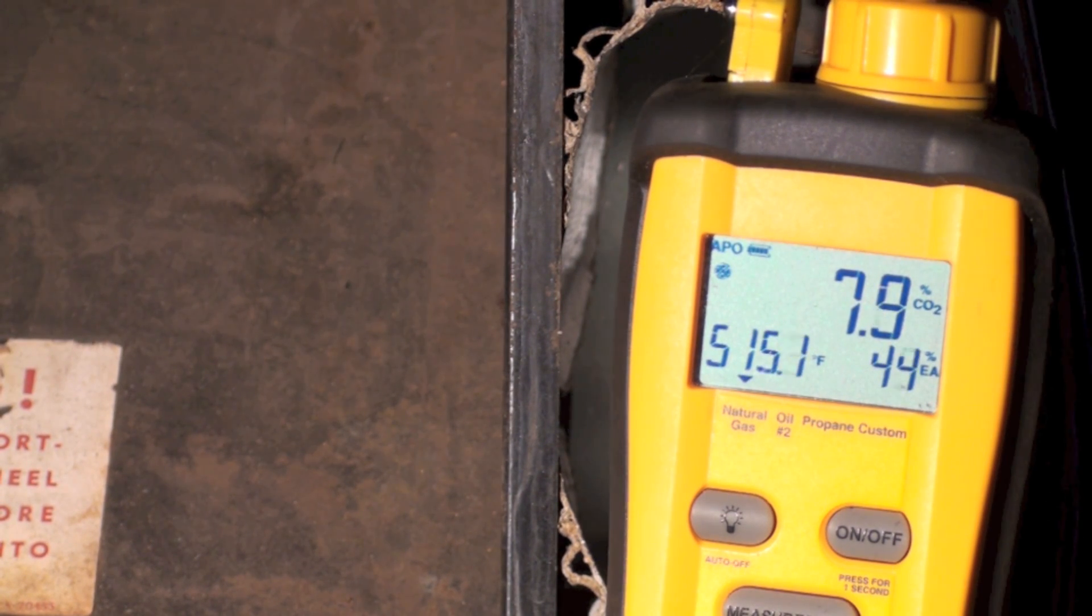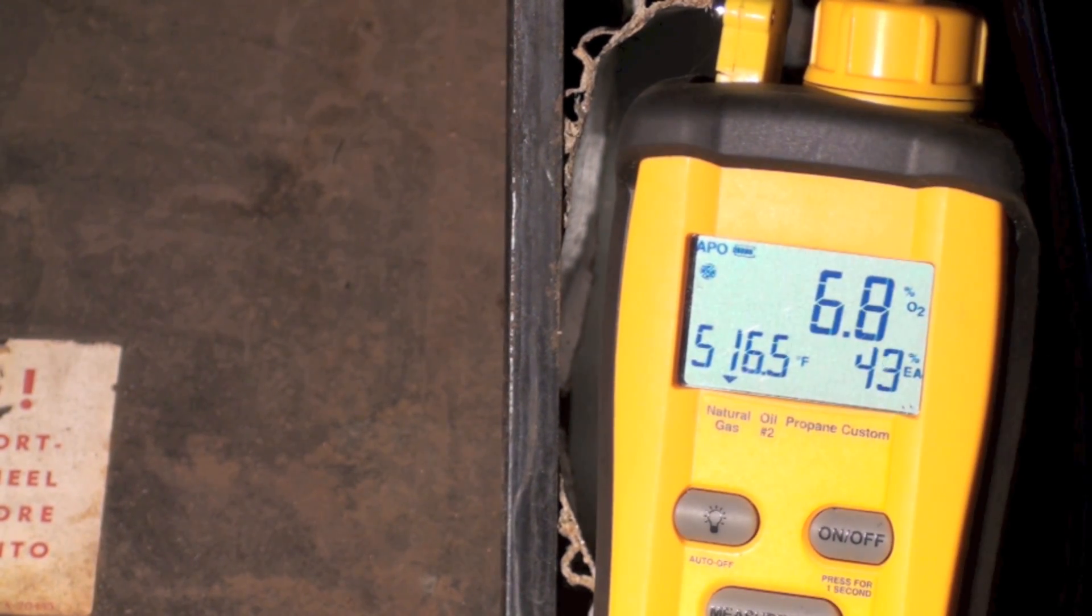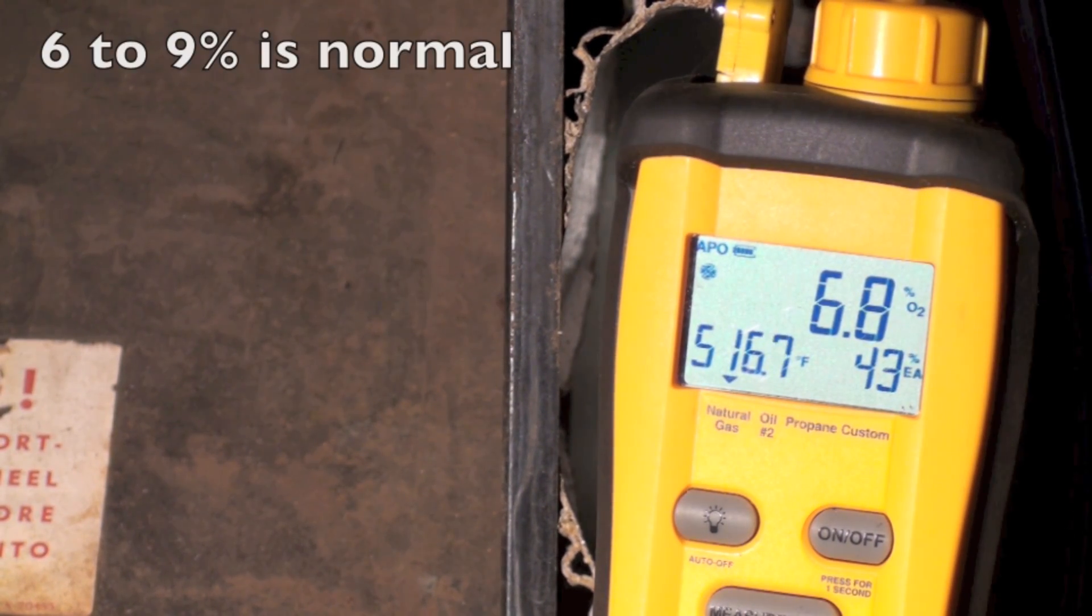Okay, my CO2 is 7.8, and I'm going to toggle that to O2 - 6.8. Look below, the stack temperature is lower.